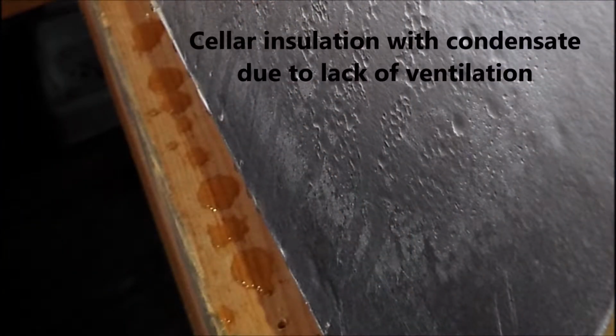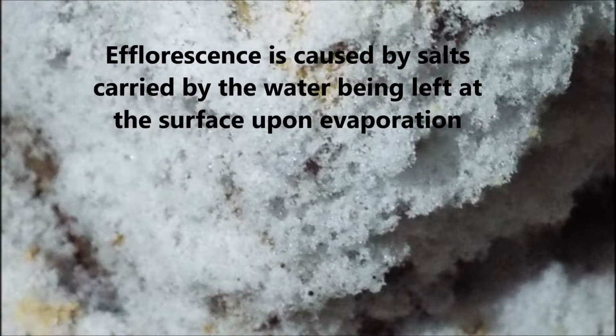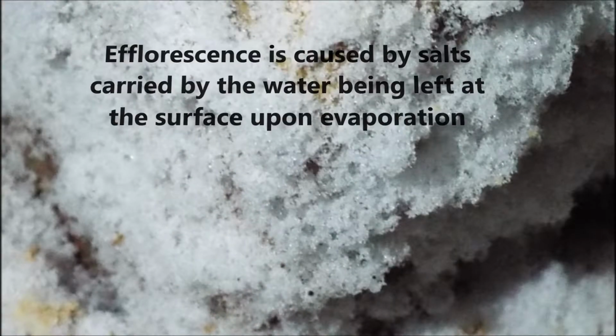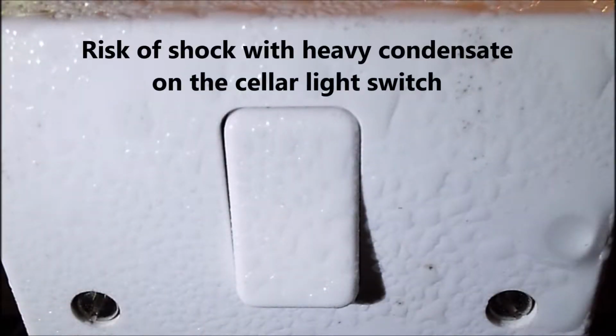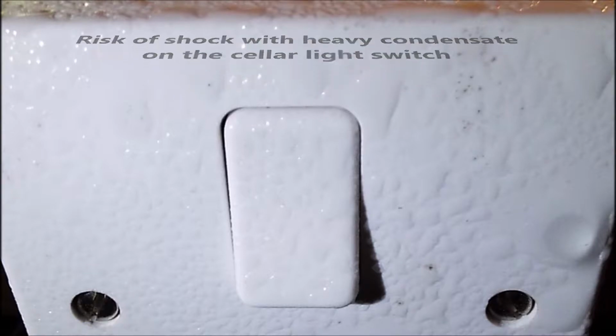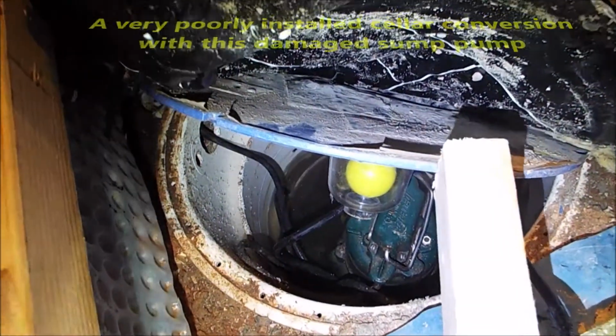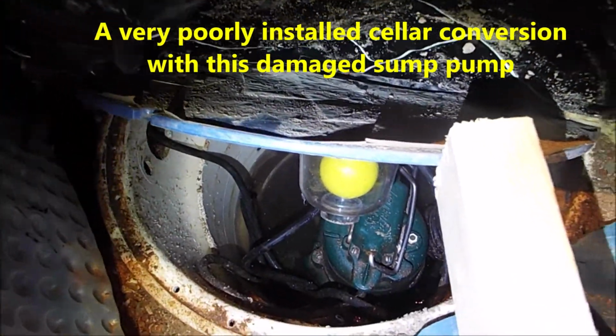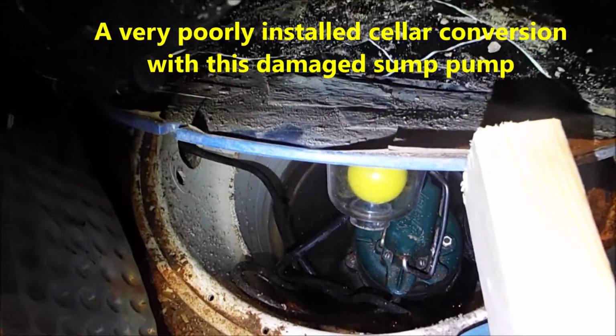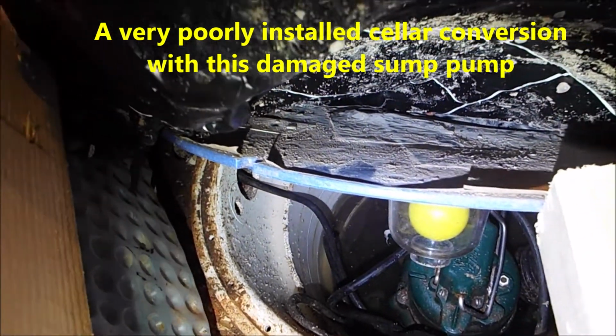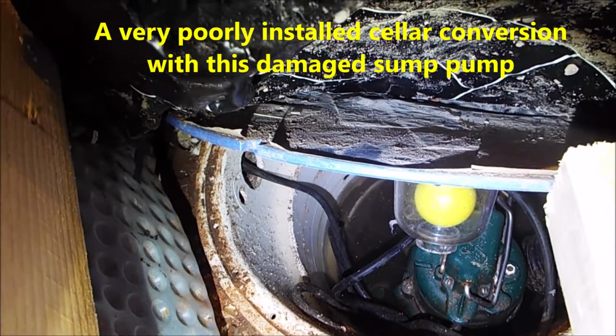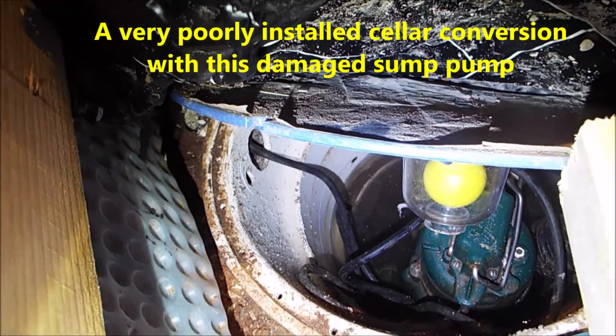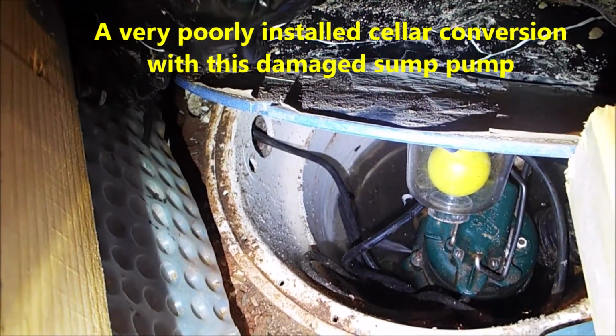Let's also not forget the cellar. If moisture migrates into this area with insufficient ventilation, it also creates problems, including short circuits. Now, this was a basement conversion that was inspected and found to be generally inadequate. Here the sump pump had not only been very badly installed, it also lost water from a fracture in its pump casting.